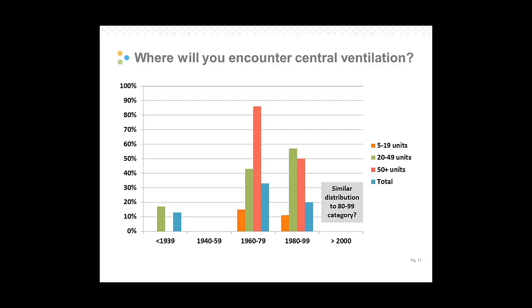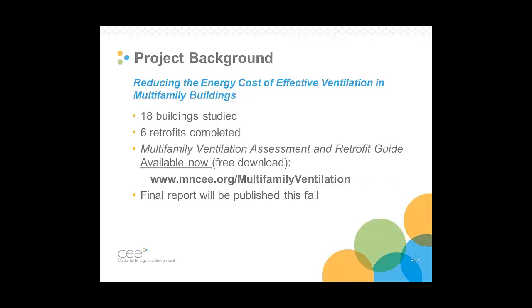Here's a look at where you might encounter central ventilation systems. So this is based on 250 or so building audits we did in the late 90s and early 2000s in Wisconsin. But you can see here that most of the centralized ventilation systems we found were in 1960s and newer buildings. And then you can also see the green and red bars are 20 to 49 and 50 plus units. So larger buildings. So 1960s and newer and larger buildings are where we're encountering central ventilation systems the most frequently.